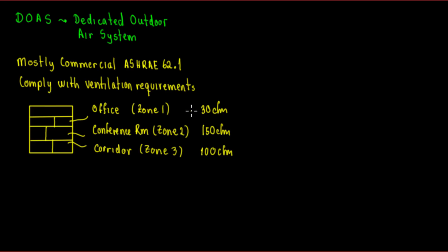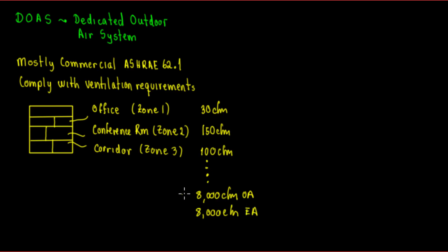After you complete your ventilation spreadsheet for all spaces, you might end up with a total of 8,000 CFM of outside air (OA). You also need to exhaust that air. For buildings, we don't try to make it neutral — we try to make it slightly positive pressure to avoid infiltration.